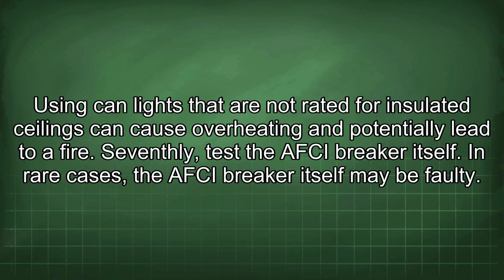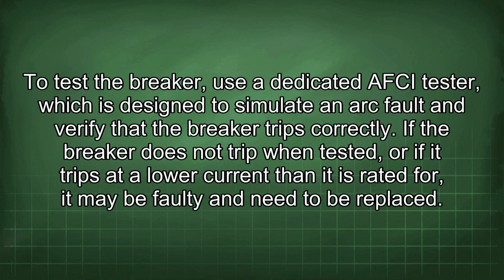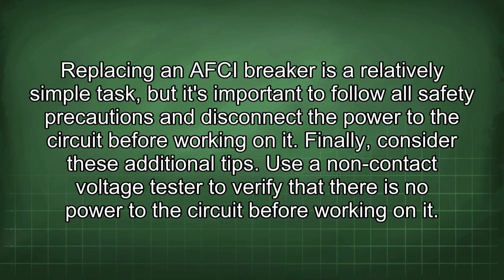Seventhly, test the AFCI breaker itself. In rare cases, the AFCI breaker itself may be faulty. To test the breaker, use a dedicated AFCI tester, which is designed to simulate an arc fault and verify that the breaker trips correctly. If the breaker does not trip when tested, or if it trips at a lower current than it is rated for, it may be faulty and need to be replaced. Replacing an AFCI breaker is a relatively simple task, but it's important to follow all safety precautions and disconnect the power to the circuit before working on it.